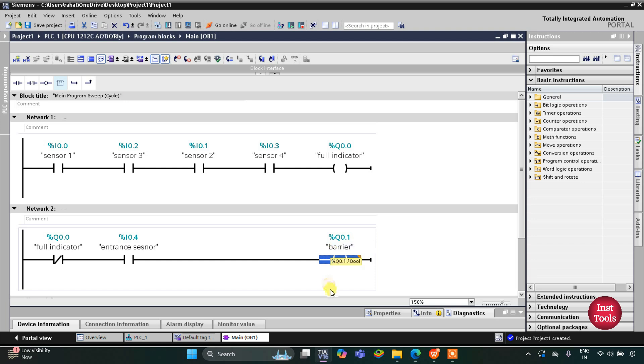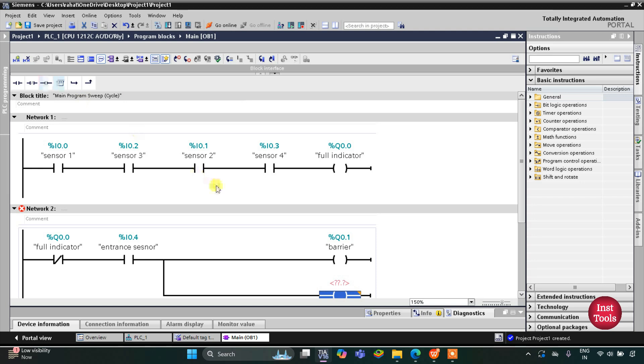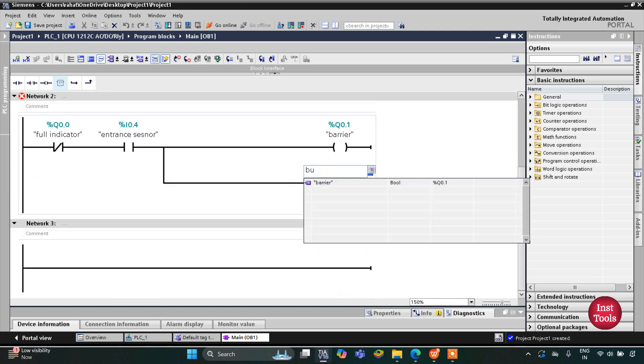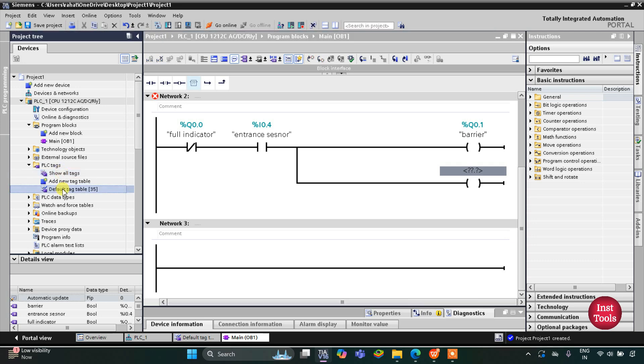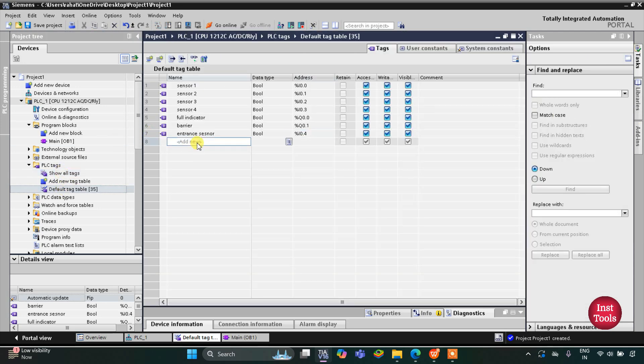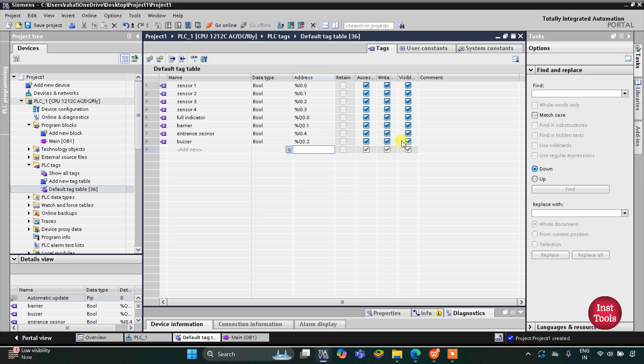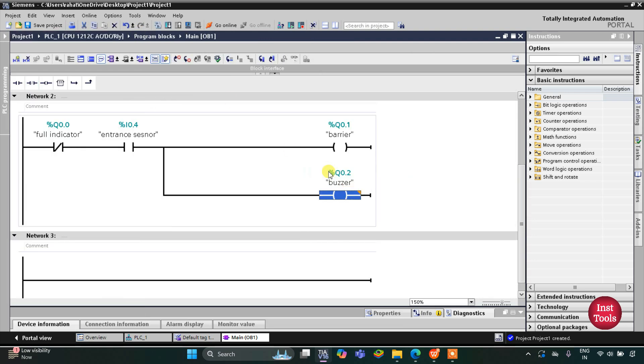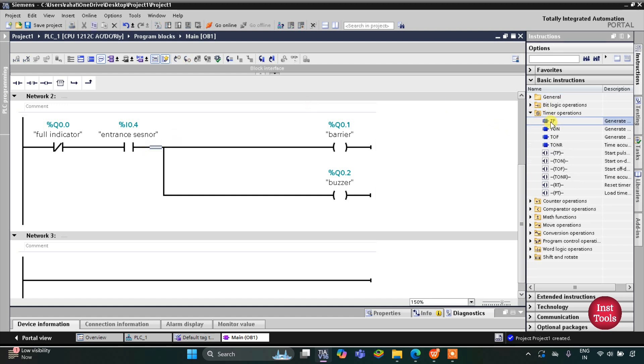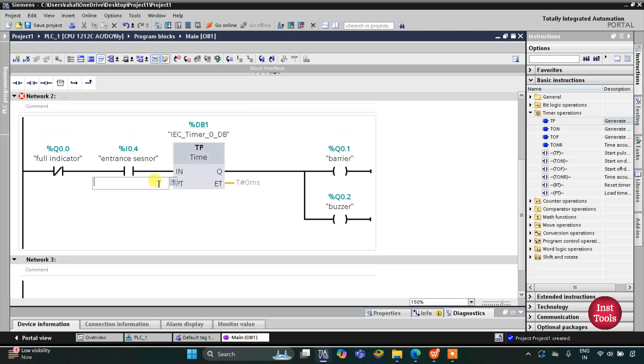With that, the buzzer should also turn on, so I'll open a branch and add a coil for the buzzer. We need to add the buzzer in the PLC tags — as it is an output its address will be Q0.2. The buzzer and barrier both should turn on for five seconds, so for that we will use a timer operation here, which will be TP, and the preset value will be five seconds.